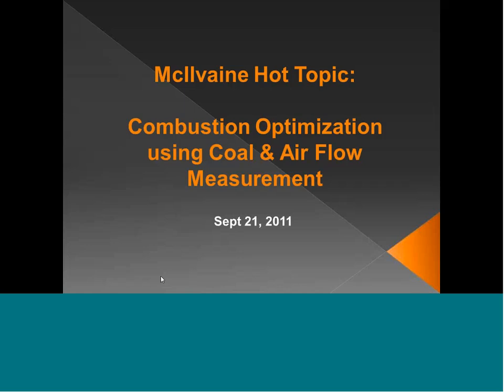Other questions? This is John Guthrie from Paragon Air Heater. I just wanted to add something on that issue of the Texas lignite erosion. Generally what we see around the world is that erosive ash usually occurs when you've got a combined silica and alumina content in the ash at 85% or above. That is certainly the case with Texas lignite and a few other coals. But generally, high ash does not automatically mean high erosion. And the experience with the lignite that you've had is similar to the experience with other components on the downstream side of the air heater. So I wouldn't be that concerned about high ash being a problem with erosion. It would be the silica and alumina content, which coincidentally also means high resistivity ash for precipitators as well. Just wanted to add that.